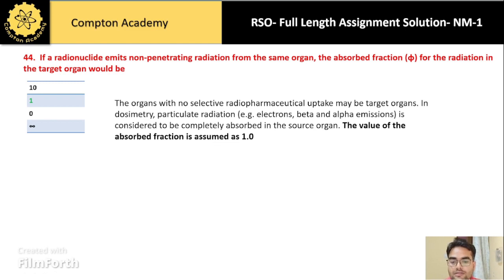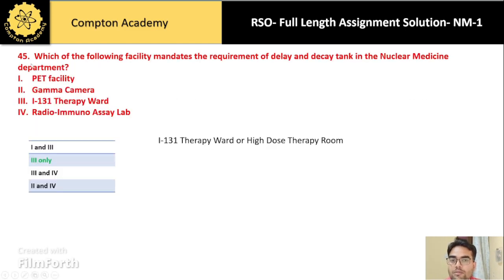Now question number 45: which of the following facilities mandates the requirement of a delay and decay tank in the nuclear medicine department? For PET-CT it is not recommended, and only for the iodine-131 therapy ward is a delay and decay tank required as per the AERB norms. So iodine-131 is the correct option for this.